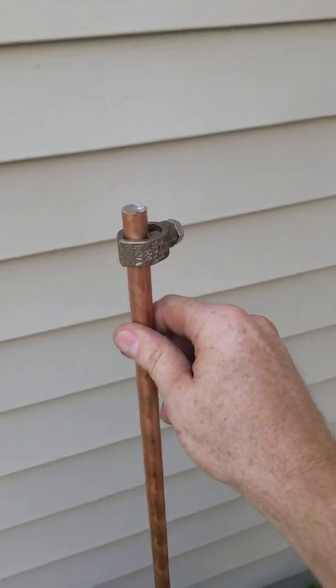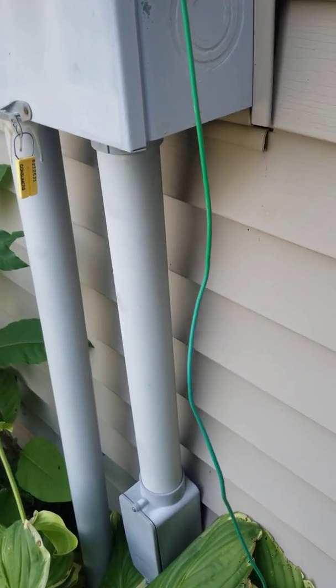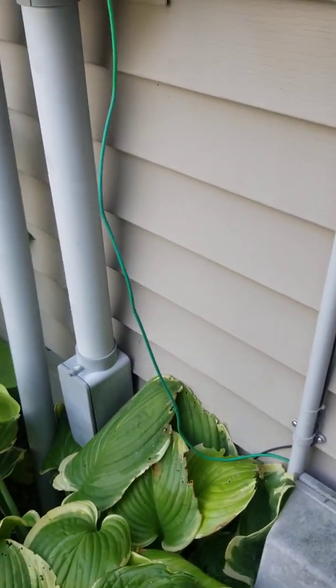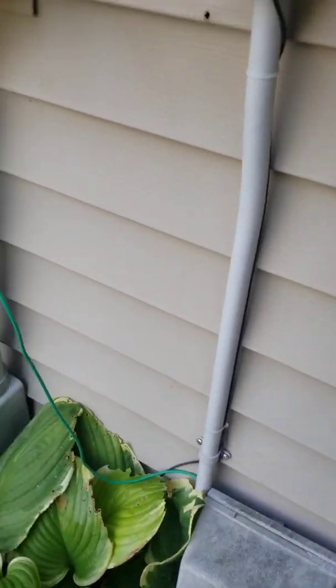The proper way to ground is to actually drive a ground rod like this into the earth. Connect this ground wire right here. And then it needs to make contact through a ground block. This is the new junction box that I'm using.